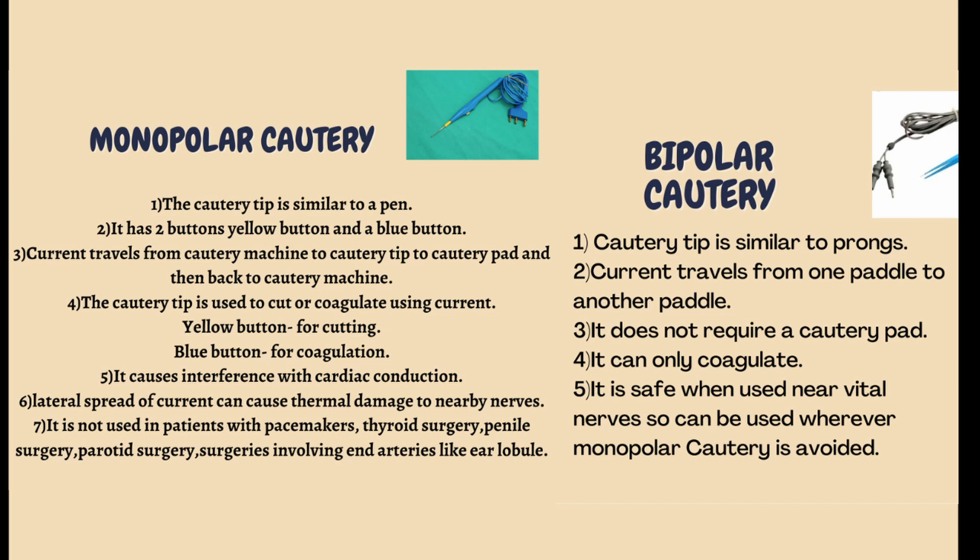In monopolar cautery, the current goes from the machine to the cautery tip, then to the cautery pad, and then back to the cautery machine. In bipolar cautery, the current travels from one paddle to the other paddle and it does not require a cautery pad.